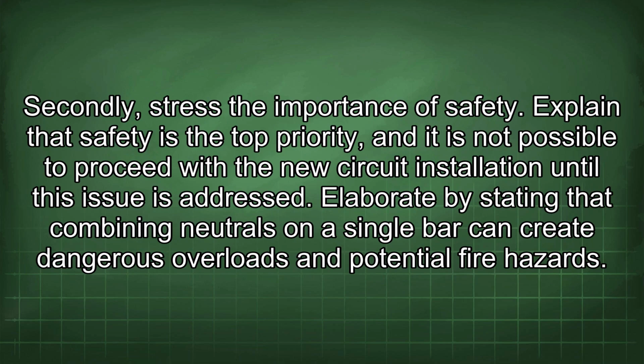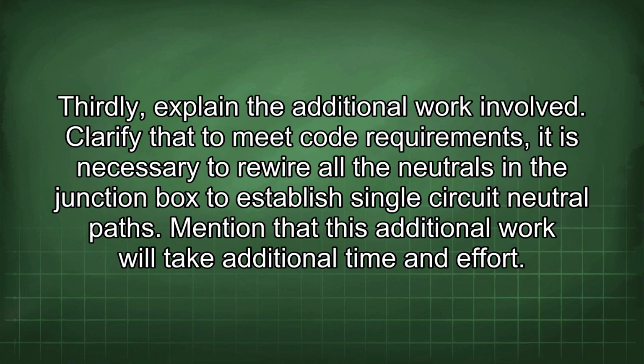Secondly, stress the importance of safety. Explain that safety is the top priority and it is not possible to proceed with the new circuit installation until this issue is addressed. Elaborate by stating that combining neutrals on a single bar can create dangerous overloads and potential fire hazards. Thirdly, explain the additional work involved.